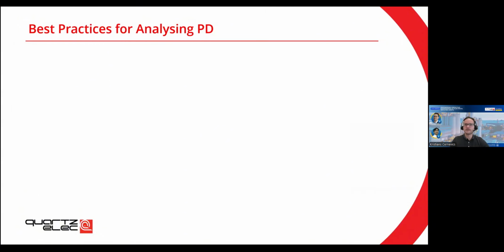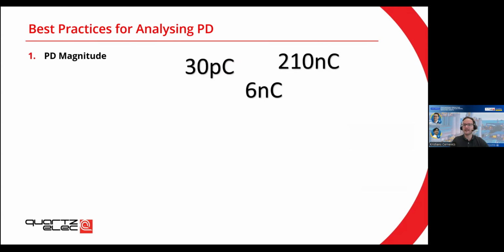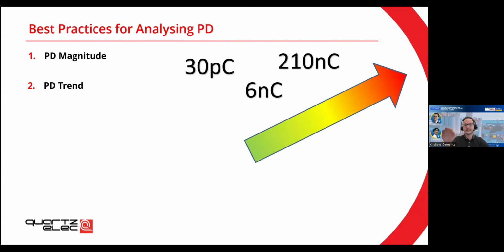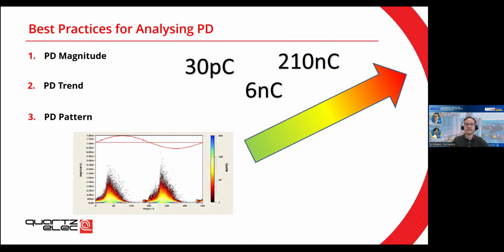So the best practice for analyzing once you get your data is, first of all, to look at the magnitude of your discharges. This will vary between different machines, but something below 5 nanocoulombs, or below 10 nanocoulombs, is considered to be in good condition. Anything above that, you might need to start to investigate. The second part is the partial discharge trend I showed you before. Do we see the trend stays the same, or do we see an increase? If we see an increase, what can we do? Do we need to schedule maintenance? Do we need to do rewinding? Do we need to cover some of the insulation? And then finally, these questions can be answered by looking at the PD patterns. Experts who know how the PD patterns look for different types of defects can then suggest what needs to be done on the machine.